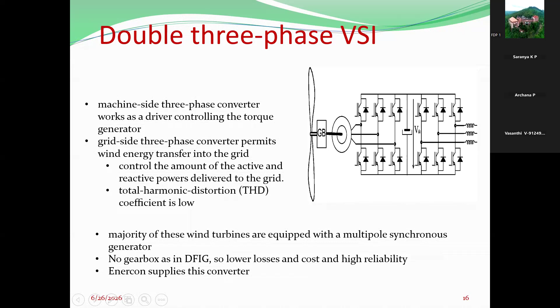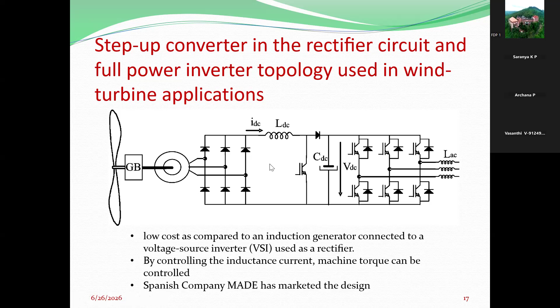Now, a step-up converter in the rectifier circuit and a full power inverter topology used in wind turbine applications. So this has a diode rectifier at the front end, and then with the help of a filter, the ripple in the DC power is controlled. An LC filter is there. Then the inverter is at this side. Then it is fed to the load. So low cost as compared to an induction generator connected to a voltage source inverter used as a rectifier. Then by controlling the inductance current, machine torque can be controlled. Then the Spanish company Made has marketed the design.